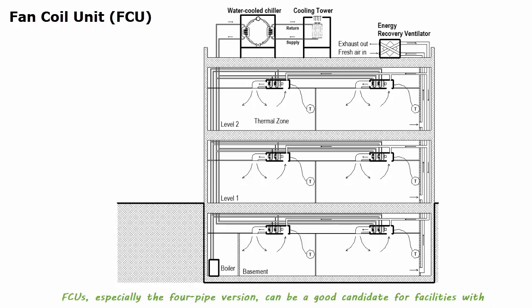Fan coil units, especially the four-pipe version, can be a good candidate for facilities with a relatively low occupant density, such as housing, residential complexes, hotels, dormitories, military facilities, etc. In either a two-pipe or a four-pipe system, dedicated fresh air intake with exhaust heat recovery should be provided to admit outdoor fresh air and maintain indoor air quality.